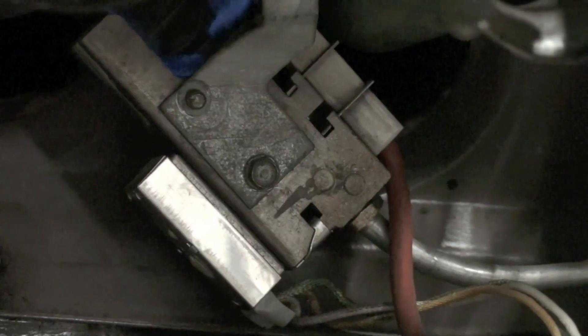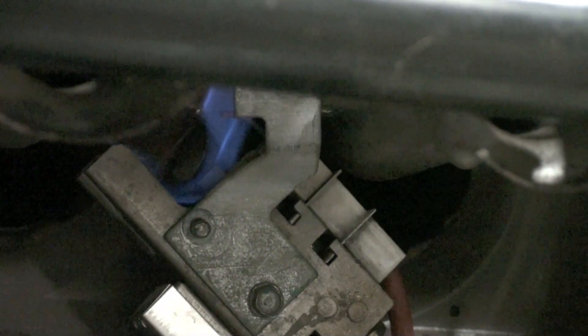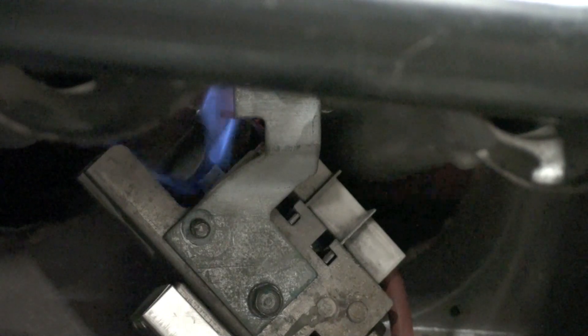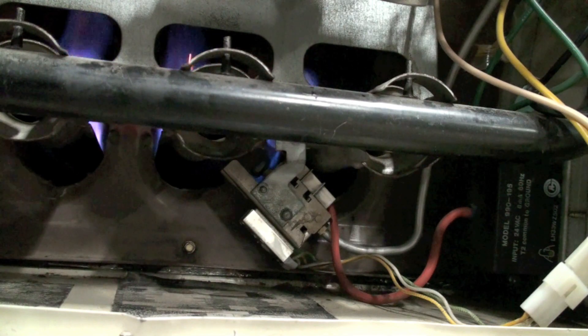You can see this is your igniter. It's an electronic box—24 volts comes into it, high-tension lead comes out. The pilot is still warming... there we go, the main gas is on and it has lit.